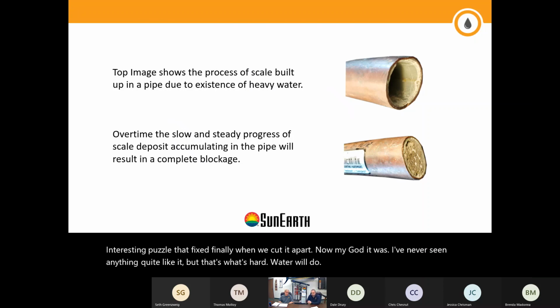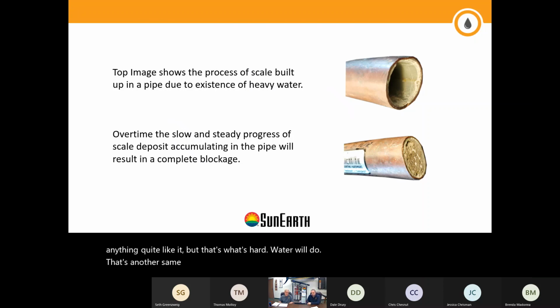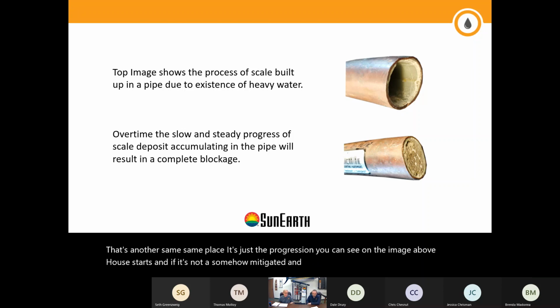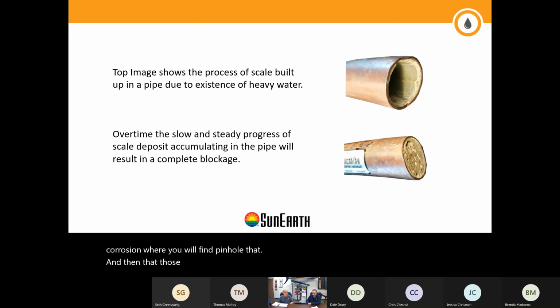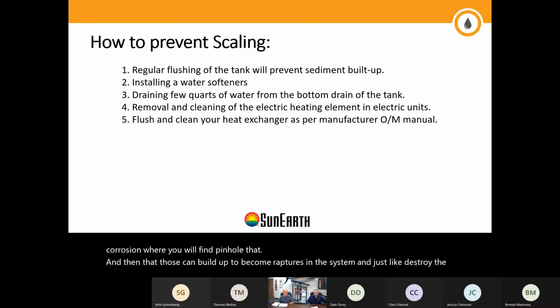That's another same place. It's just a progression. You can see on the image above how it starts. And if it's not somehow mitigated, it will lead to that complete blockage. And this is obviously the example of scaling. And then the other side will be corrosion, where you will find pinholes, and those can build up to become ruptures in the system and just destroy the pipes completely.